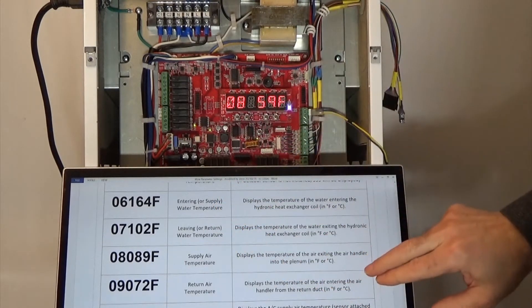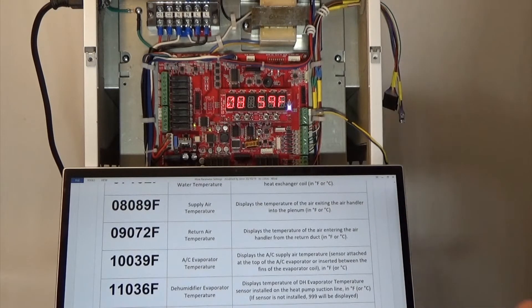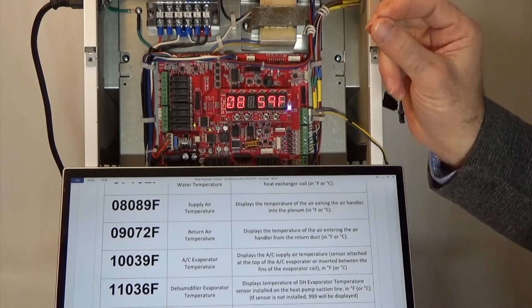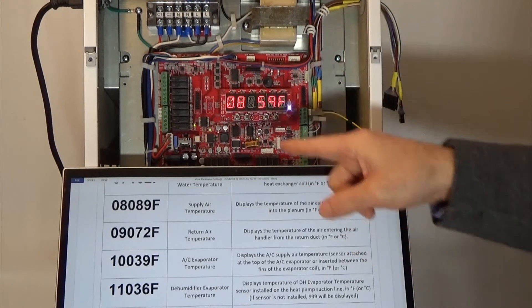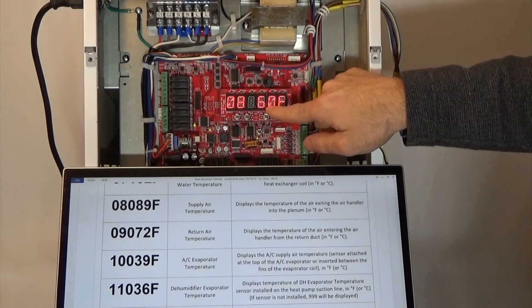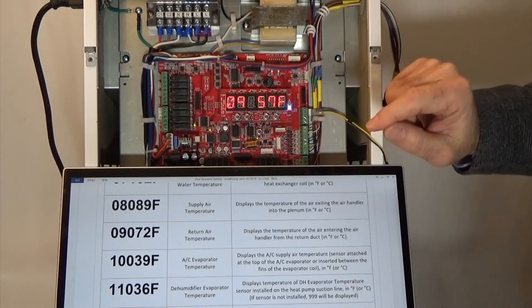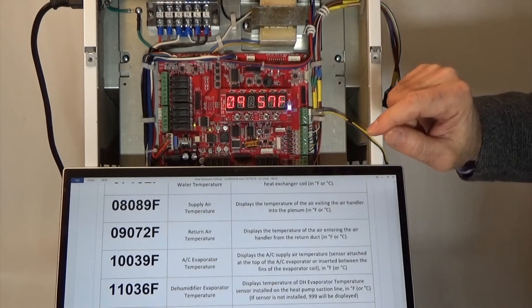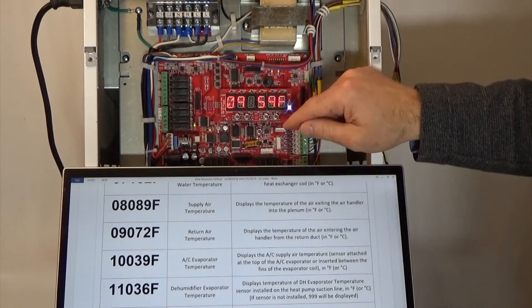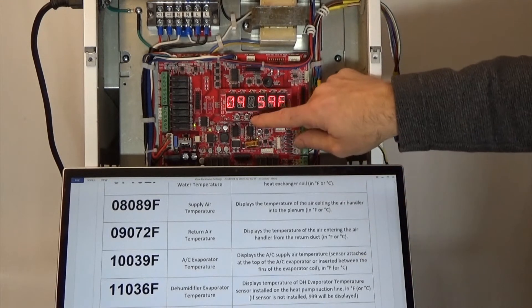Parameter number eight is the same on the air side. Parameter number four gave us the air temperature delta T. In parameter eight, we get the supply air temperature. In parameter nine, we have the return air temperature. Because the unit is not operating, it makes sense that those sensors are very close together in terms of readings, which they are.